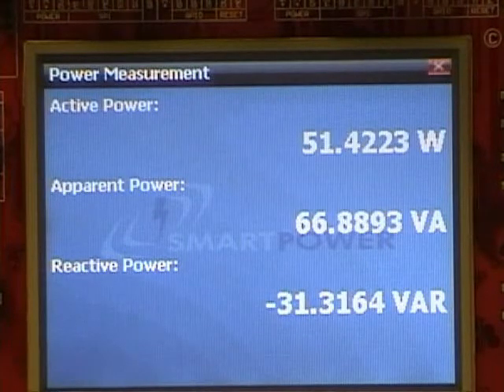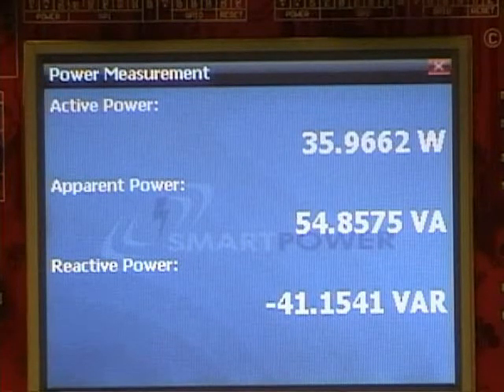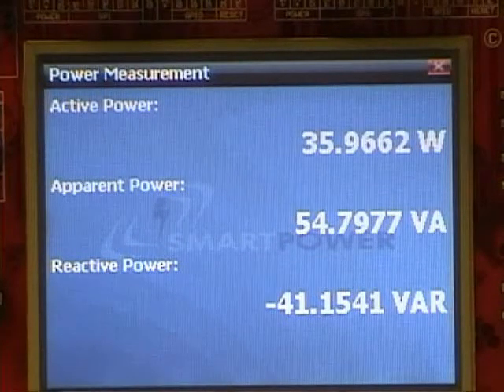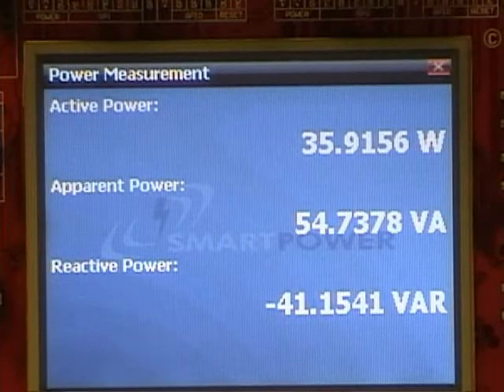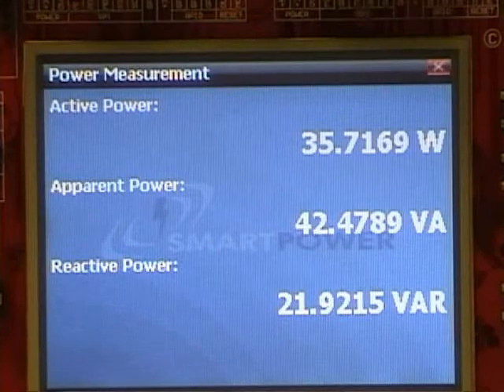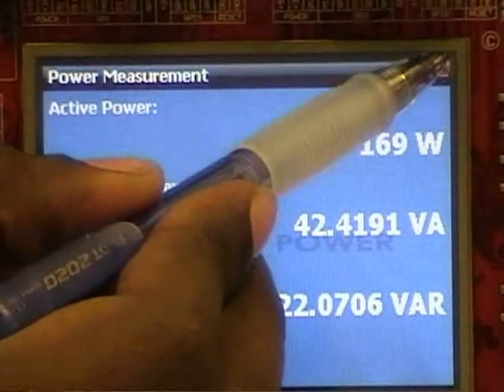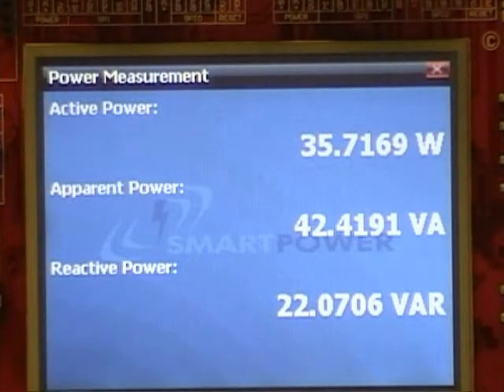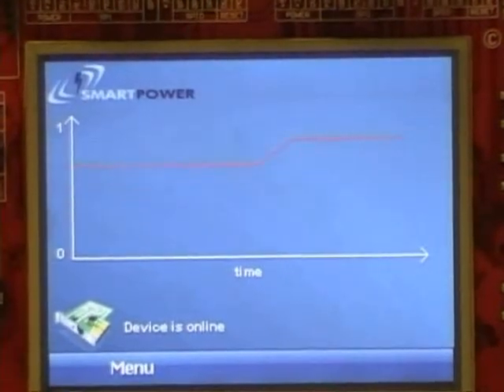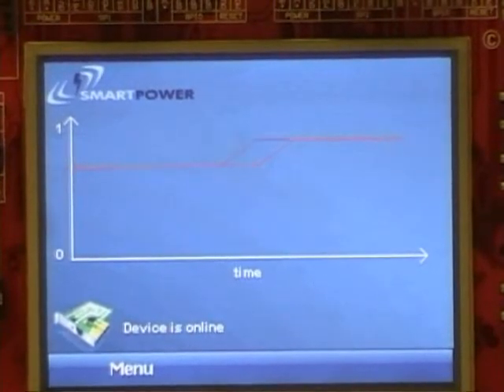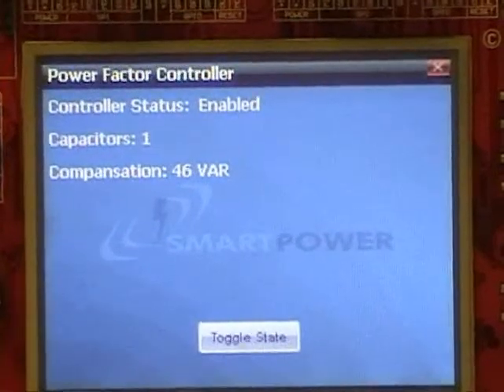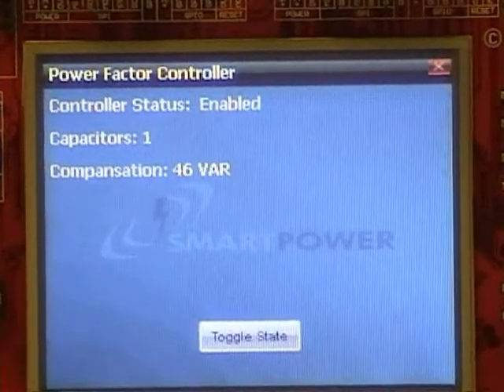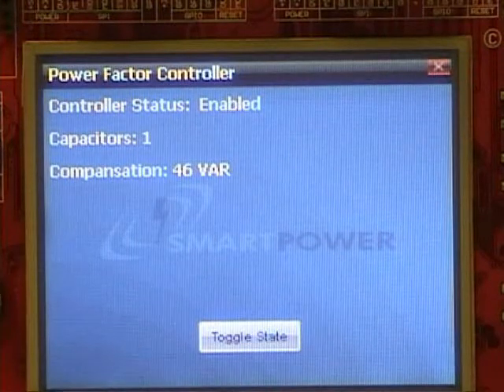Now we reduce the inductive load. The power factor controller will monitor the change and automatically deactivate capacitors so that the power factor is maintained within the designated threshold. Now the power factor controller window shows that only one capacitor is currently turned on.